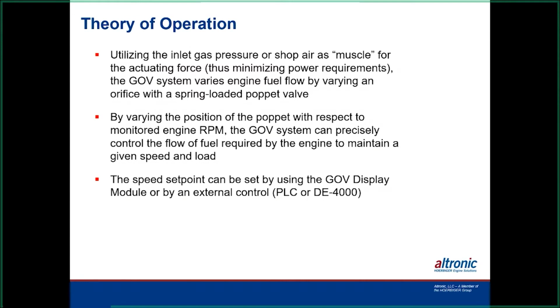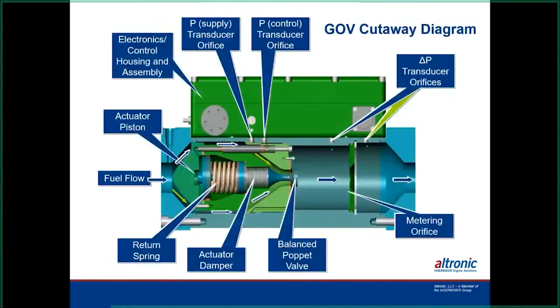And like I say, by varying the poppet, you control the RPM to the engine. It just moves back and forth, changing the orifice size in there. So the speed set point can be set up using the display, like I said earlier, or an external PLC or DE4000. And this gives you a good illustration of the inside on it there. So you can see how the gas flows around the poppet.